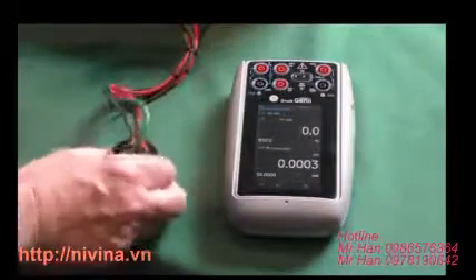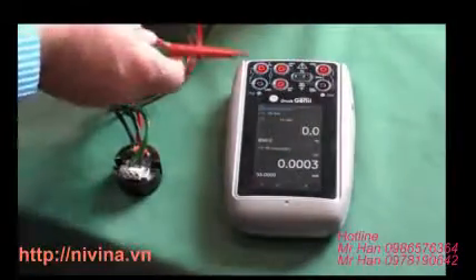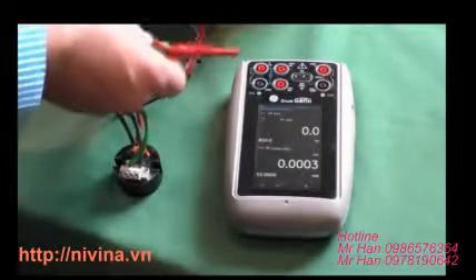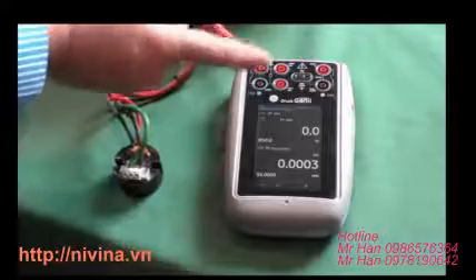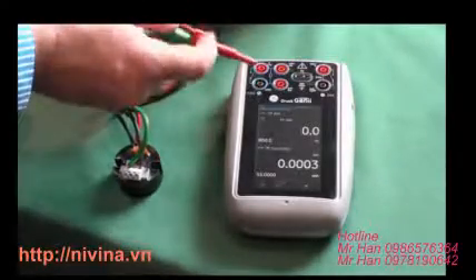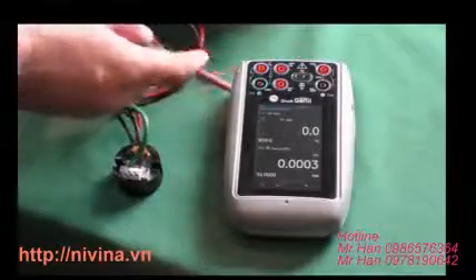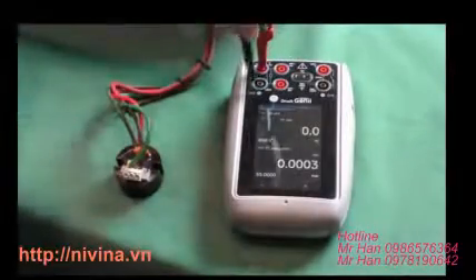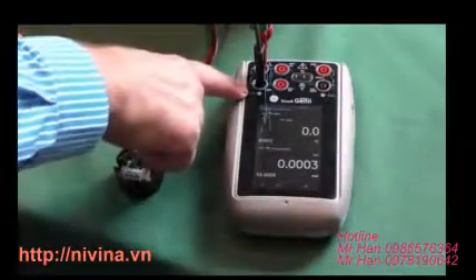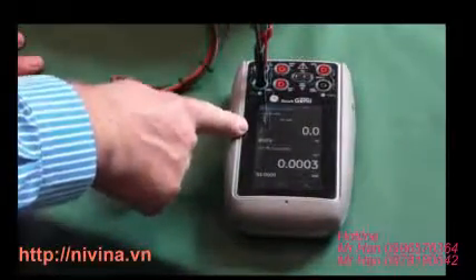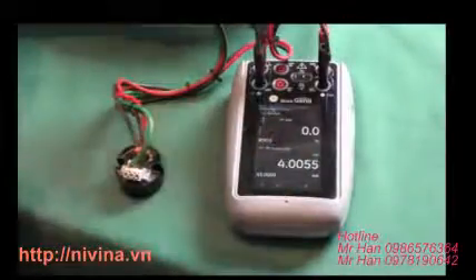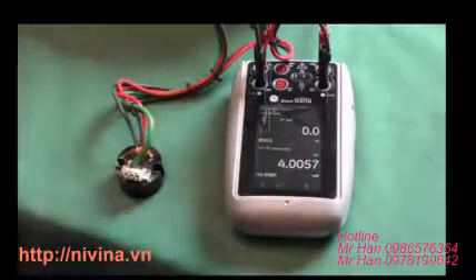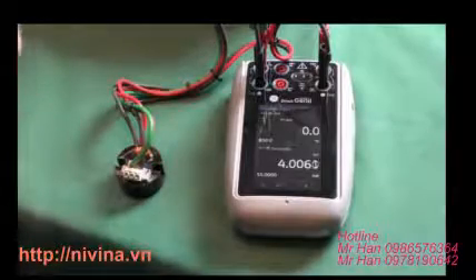So here I have a rather old RTD transmitter. It's a 3-wire. When we're actually sourcing or simulating, we don't need to connect all 3 wires independently. So what I've done is I've joined the compensation wires together there. We make a simple connection on this side. It doesn't matter which way around I do this, it's a resistance. So that's channel 1. If we look on here, channel 1 is degrees C. Now it's a transmitter, so as you remember before, we've got 24 volt supply on channel 2. Connect that in, and straight away 0 degrees C is 4 milliamps. So this is PT100, 0 to 100 degrees C.